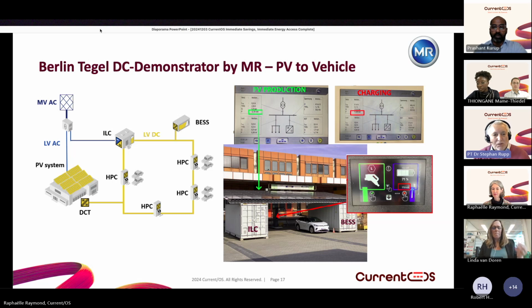That's the congestion type that we've seen in the beginning. But what you could get is a grid connection of half the connectivity. So for an 800 kilowatt installation, you just get 400 kilowatts. Because you have the DC connection, you can take off half of the load and directly feed it into the battery, relieving stress from the power grid. At the same time, you are economizing on converter losses because now the direct current goes directly to the battery and you take it from here to charge vehicles.